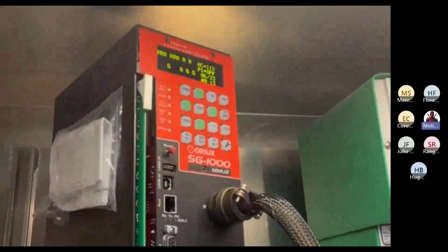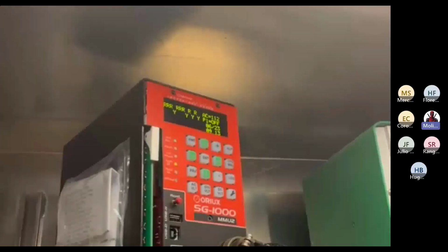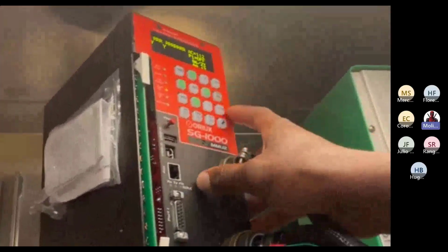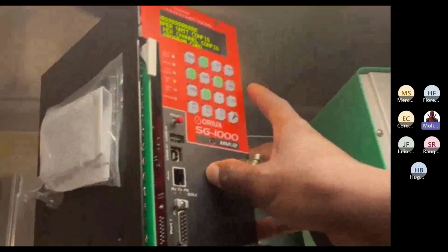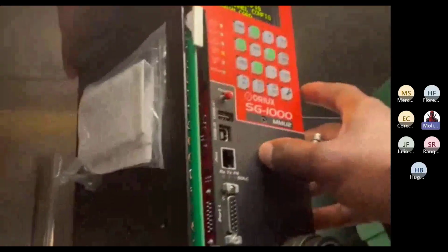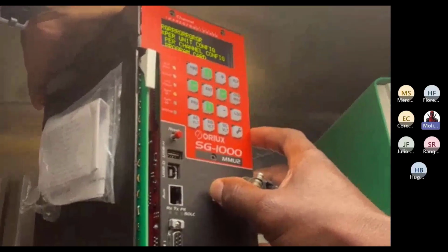Now, the main difference is the way you set it up. I honestly think it's a much more logical step-by-step, like you're going down a list. When I walk somebody through setting up, the first thing you do is hit the config menu button. Here, let's take a look at it. If you just hit config menu, it should be on the right side. And then the per channel config: you go down arrow once and then enter.